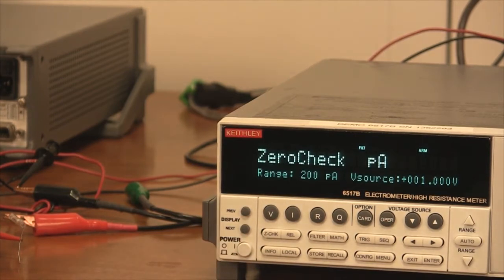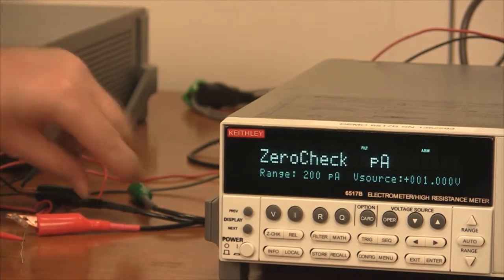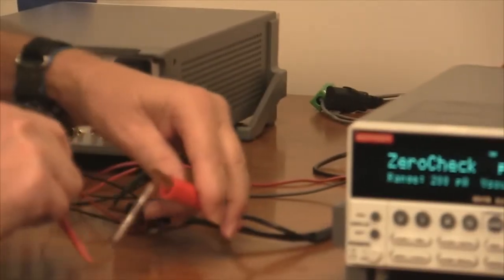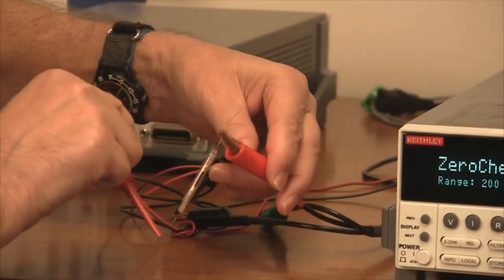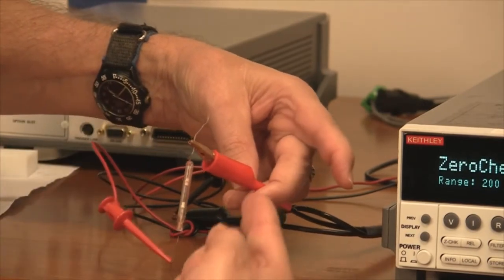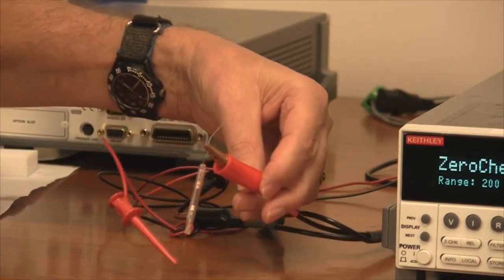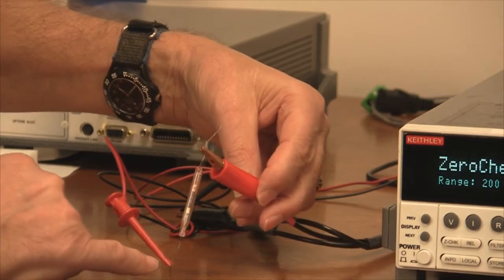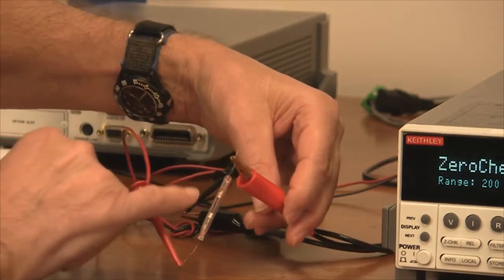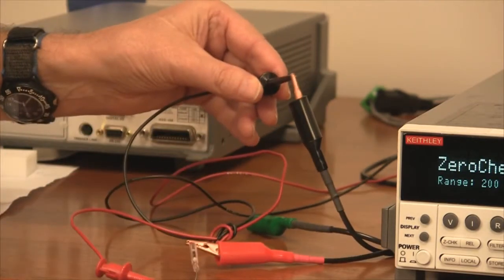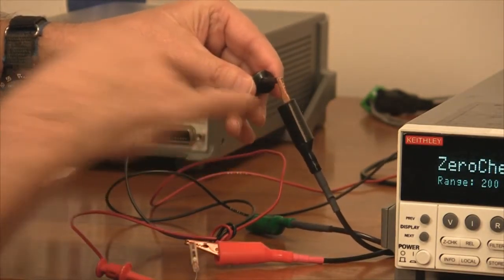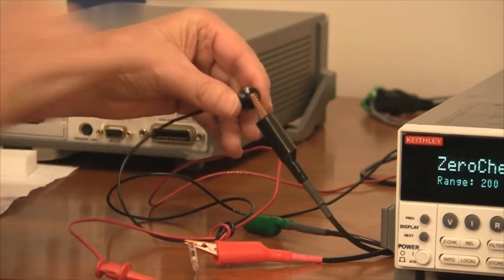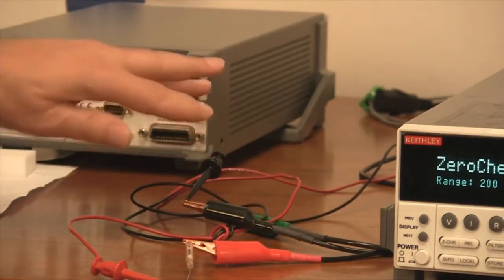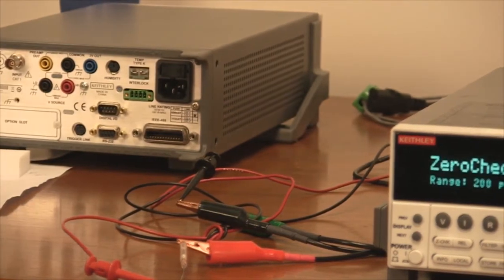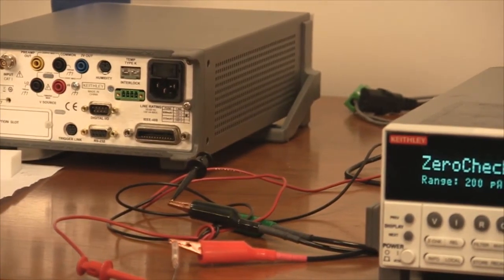I wanted to show you how it's connected. What I have here is a 1 teraohm resistor. This here is input high. The other side of the resistor is voltage source high. It's a simple series circuit, and we have the two lows connected together, input low and voltage source low. Now you don't have to physically connect those two. You can use the meter connect feature of the instrument, shown in another video.